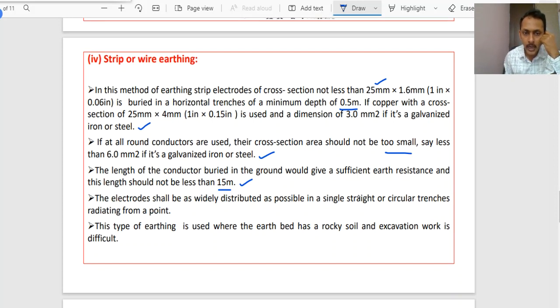Now the electrodes shall be distributed as widely as possible in a single straight or circular trenches radiating from a point. This type of earthing will be used where we have rocky soil and the excavation or digging work is very difficult. Then you can go for the strip or wire earthing method. If the earth is soily in nature, then other types of earthing can be preferred. But if the earth is rocky in nature and digging or excavation work is difficult, then you can go for the strip or wire earthing.